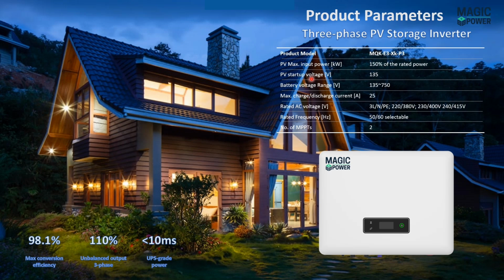The startup voltage for the PV and battery is 135. Charging and discharging current is 25 ampere. Rated AC voltages could be 380, 400, and 415 depending on the grid standard. Similarly, the frequency is selectable, and then the number of MPPTs. There are two MPPTs for this system.